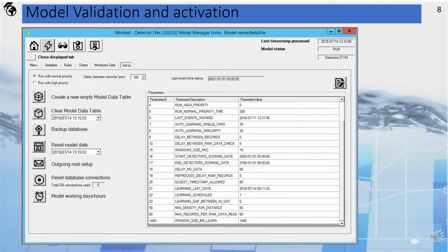An additional setting that should be defined is the automatic learning policy. This policy defines at which time intervals the model's auto-learning is performed. Auto-learning creates the statistical limits and all other single-parameter statistics. It also creates the similarity table. In order to activate auto-learning, please set the value of the first variable in the red box to 1. The second variable sets the time interval in days in which this auto-learning occurs.